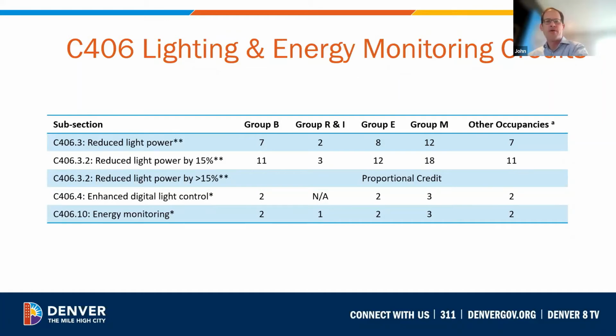Enhanced digital lighting control is a credit available to all occupancy groups except residential multifamily buildings. This credit requires advanced control capabilities, including continuous dimming and load shedding, as well as individually addressable luminaires. A common system that can achieve this is luminaire level lighting controls, or LLLC. These systems have great savings potential by enabling control of individual or a small group of luminaires to either dim or shut off in response to occupancy, daylight levels, or other factors.